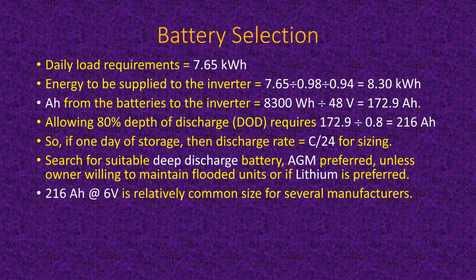So 216 amp hours at 6 volts is a fairly common battery. And if you multiply 6 times 216, you notice that that's a little over about 1,300 watt hours, which if you use just 1,000 of those, that's a kilowatt hour. So this is basically a kilowatt hour of storage that we're looking at here for one battery. And if we have 8 of them in series, then we've got 8 kilowatt hours of useful available electricity.